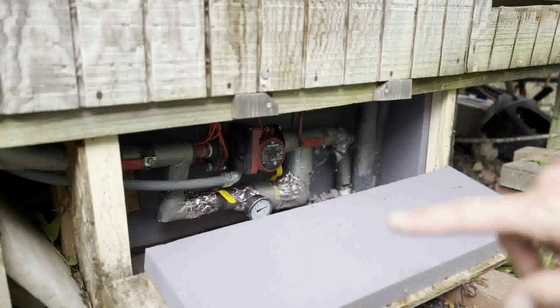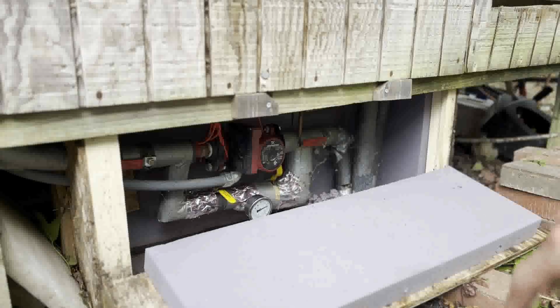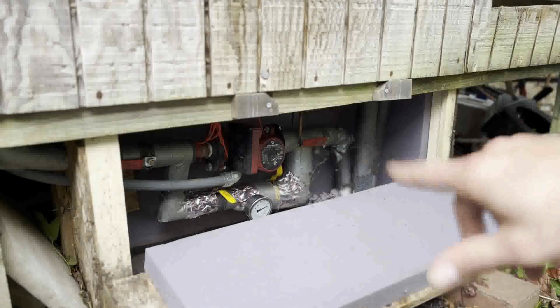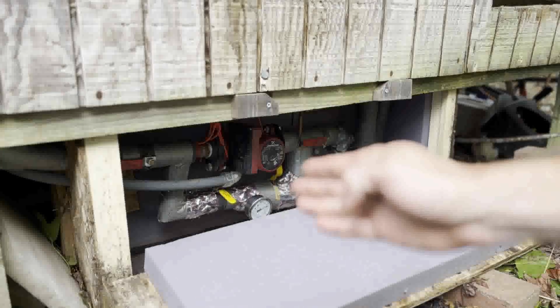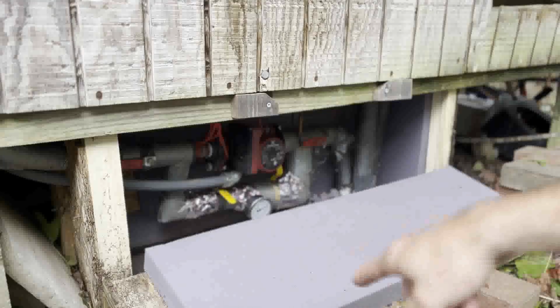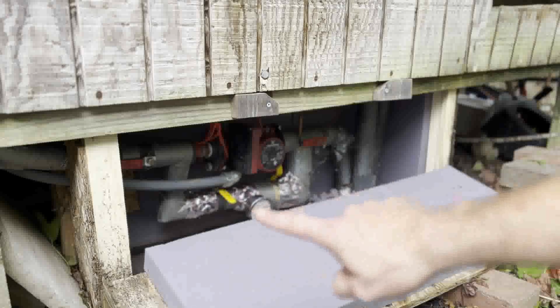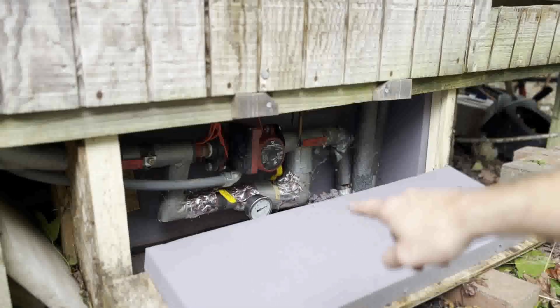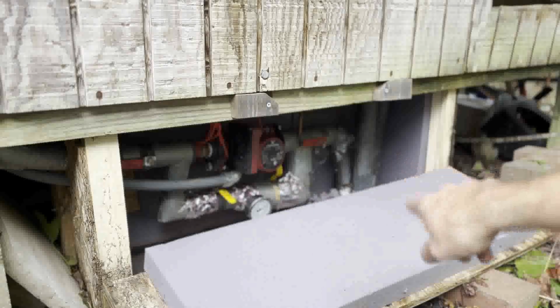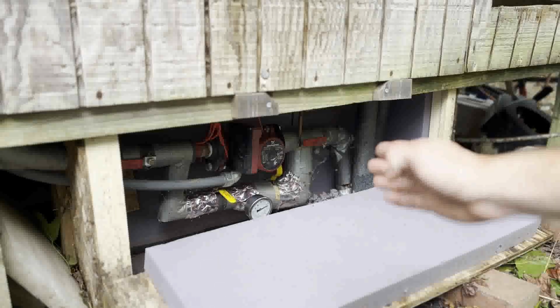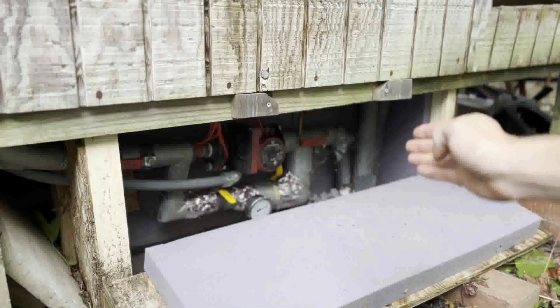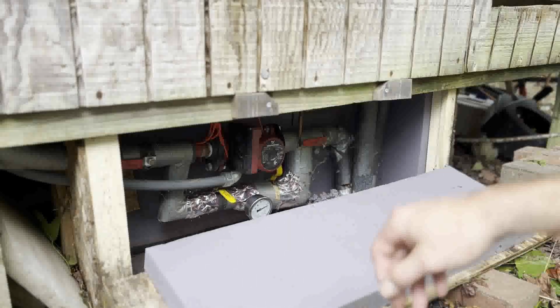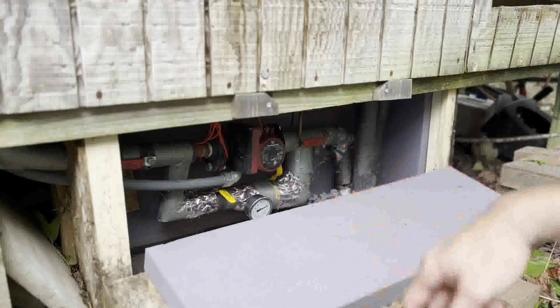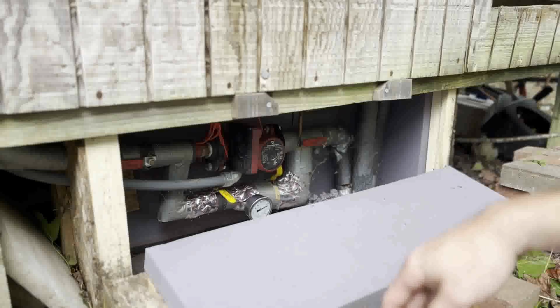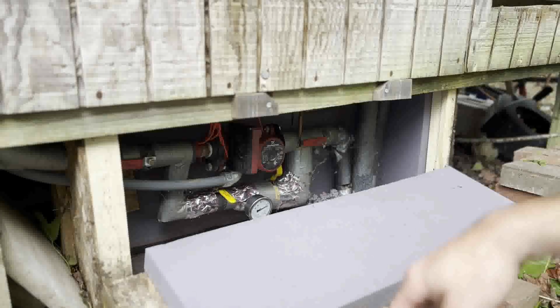That extra stuff you see on the bottom is just valving that is normally closed that you can use to check your pump flow on your pump curve. Basically, you need a way to measure the net static head, so you need the discharge pressure. I would open that first valve, close the back one while the pump's running, and note the pressure. Then I would close that valve and open the back valve, and note the pressure. If it was, I'm just throwing numbers out, 30 and 20, the static head would be 10. And you can use the pump curve from the manufacturer. Every manufacturer that makes a pump has pump curves for all their pumps, so you can test and calibrate your flows and see what you're actually moving.